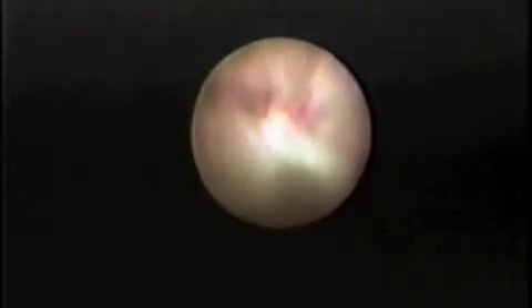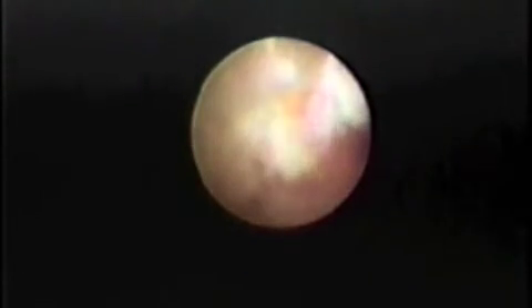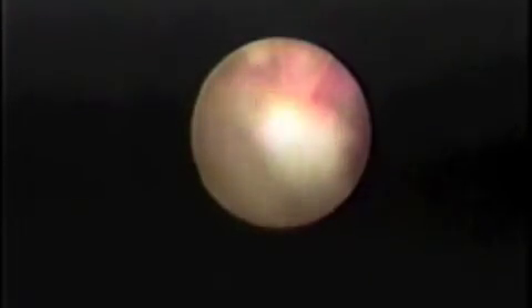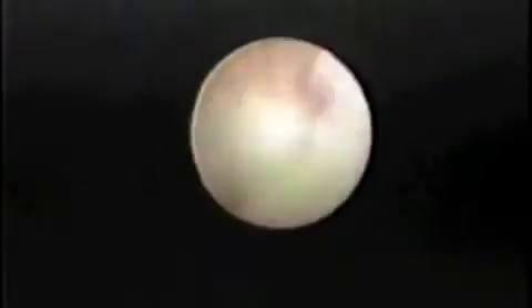There are 2 ways to do this. 1, just move the endoscope forward. 2, you can turn the laser fiber advancement knob at the rear of the laser endoscope handle clockwise. Using this knob, you can position the laser fiber from 1 to 6 millimeters from the endoscope's distal end. Remember that the distal end of the endoscope is radio-opaque, so on fluoro the laser fiber can extend up to an additional 6 millimeters. Don't bury the laser fiber in tissue. That can lead to overheating.